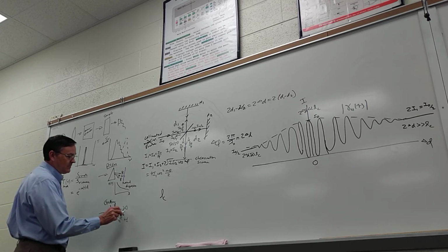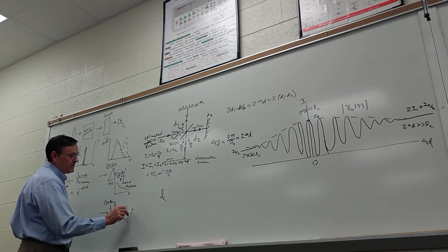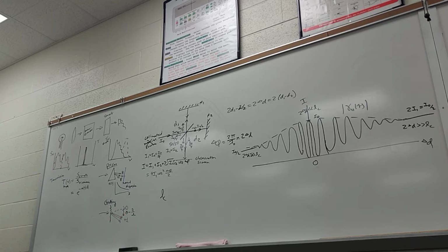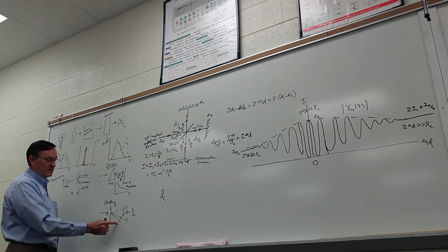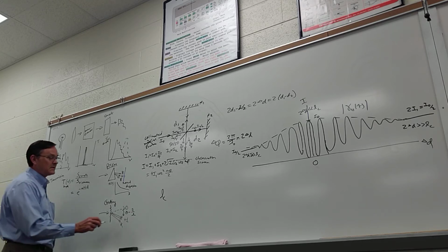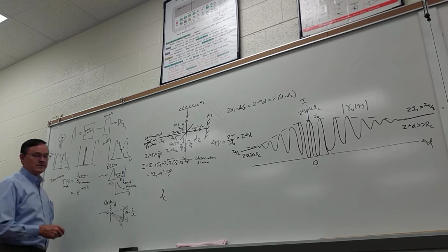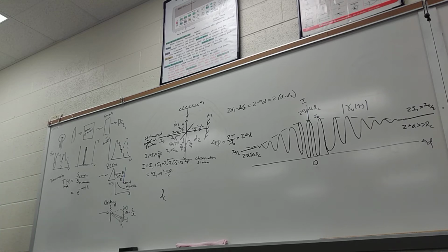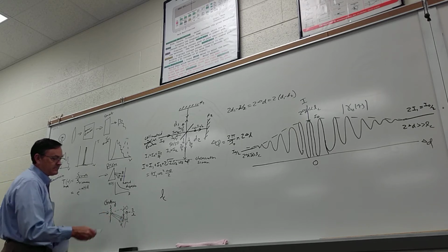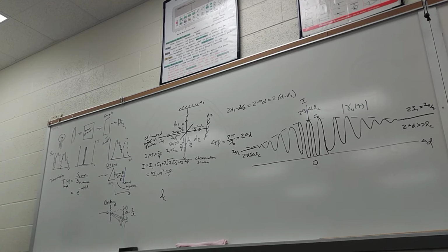So this angle, theta, goes as wavelength divided by the period of the grating. The period of the grating is fixed. So that means red light is going to deviate more in angle because it has a bigger wavelength. So it's exactly the opposite. And here again, you can just take an opaque screen with a little slit, scan it, and now you've got a monochromator. Okay, so now we know how this monochromator is made.